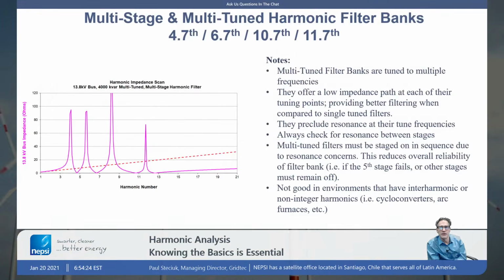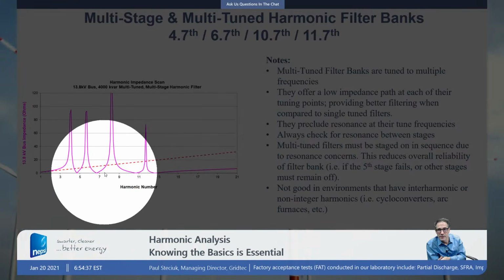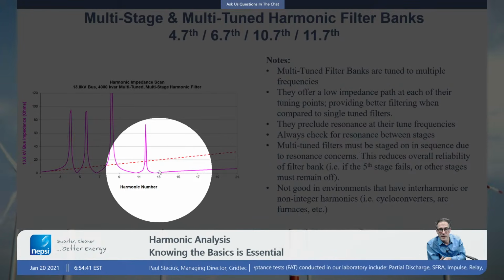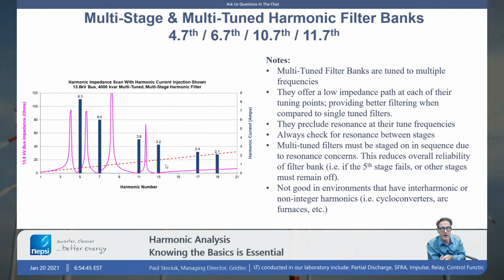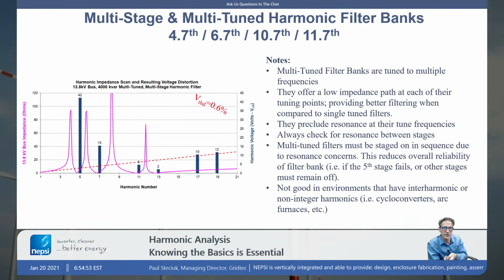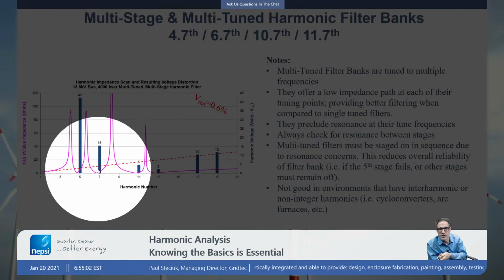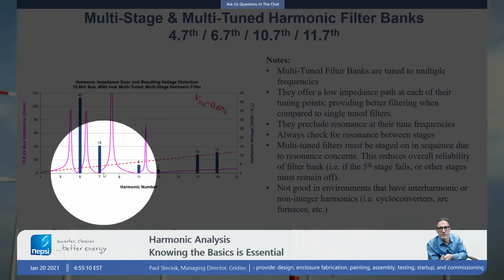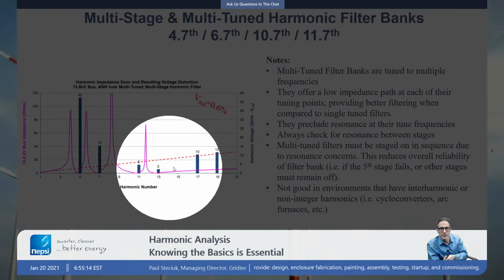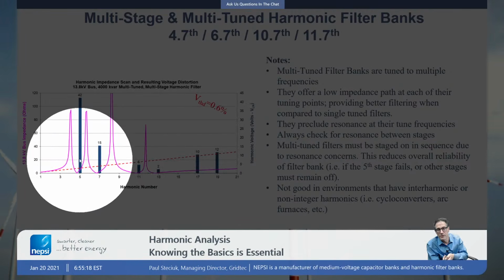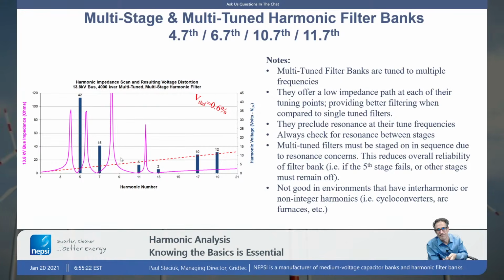So multi-tuned filters are often used in complex networks with high harmonic current injection. And again, here we have a 5th, 7th, 11th, and 13th harmonic filter. You can see that I've basically effectively dropped the impedance significantly at those harmonics by putting a filter at each one of those tuned frequencies. And the result, if I did that current injection here, is that the VTHD drops off significantly. It's a significant drop in voltage distortion, and it's because of V equals I times Z. I is the current injection. That value remains the same throughout all this analysis. The Z of the network is decreased because we put filters at each one of these frequencies. So you've got your dashed reference line here versus the impedance curve of the filter.